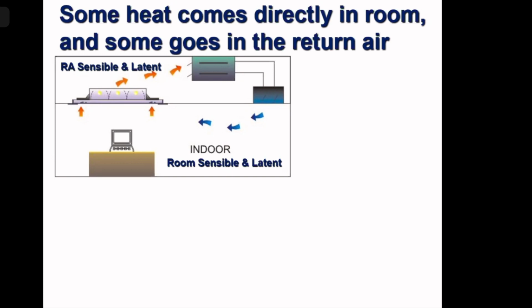You see, the bottom part is the indoor room. And then we have a false ceiling. Above the false ceiling, we have a dark colored air handling unit, inside which there is a cooling coil. And there is a fan which supplies air, and we take it through a ducting and supply it by a supply air diffuser. You can see the blue color diffuser with blue color cold supply air. And then we take it in the return air by the return air diffuser, red return air. Supply air, let us say 12 degrees centigrade, picks up all the room heat and becomes 24 degrees centigrade.